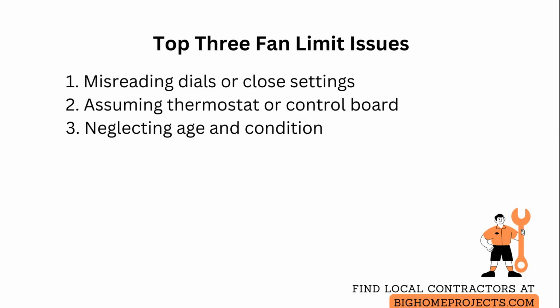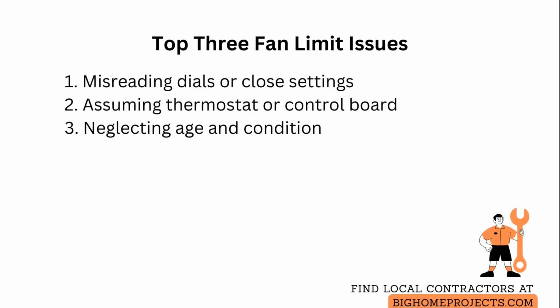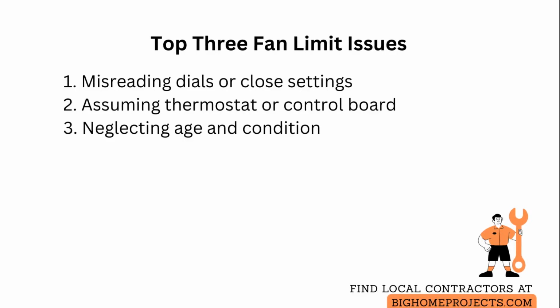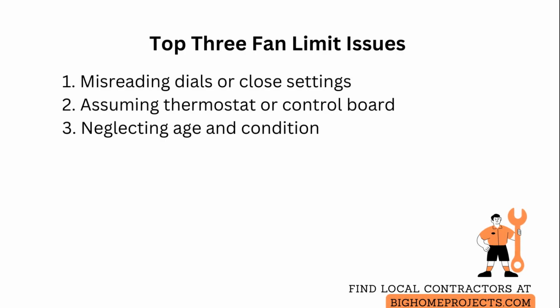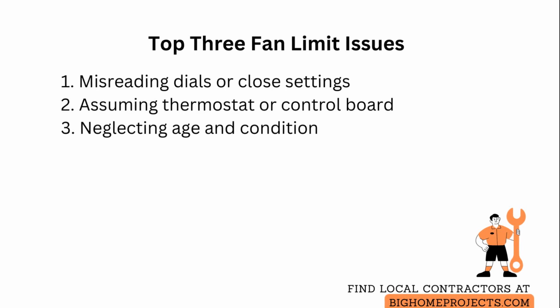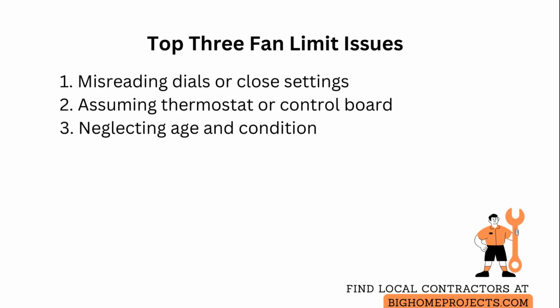Another frequent issue is assuming the thermostat or control board is faulty when the fan limit is out of calibration. Verify plenum temperature with a handheld thermometer at the sensor before swapping other parts. A third problem is neglecting the age and condition of the control.